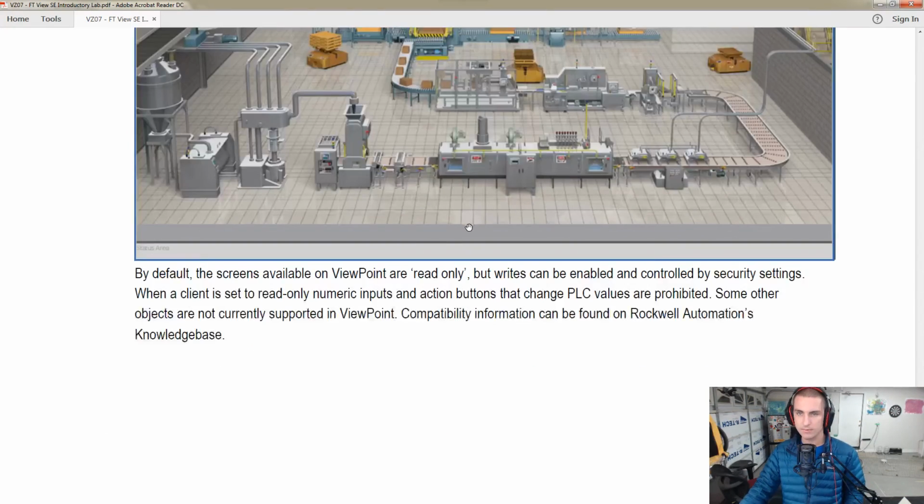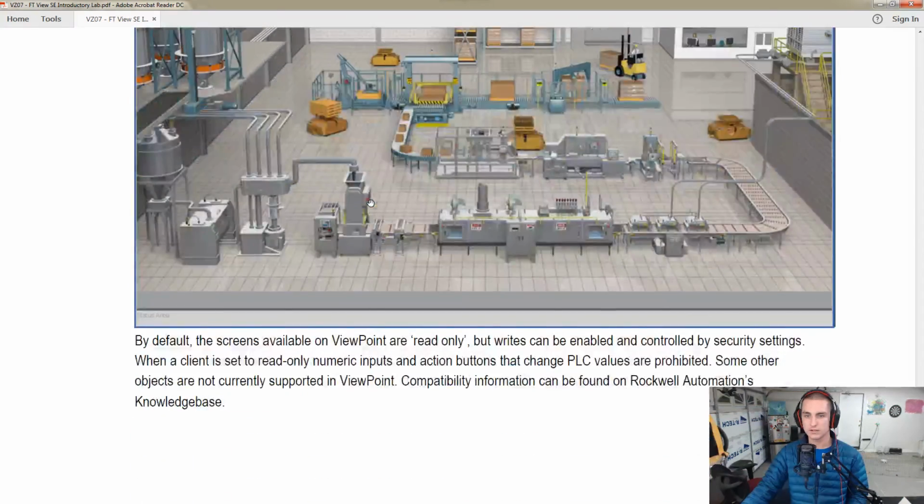But basically, assuming that's set up correctly, assuming you've gone through the installation process, or you used Rockwell's virtual appliance images that you can just load into your virtual server. Let's say you have VMware, you can drop in a FactoryTalk View server VM, historian VM. You can just drop these in, and all the software is already pre-configured. You just license it. So that could save a lot of time and prevent software installation mistakes. But yeah, I know the web server is always kind of a tricky one with any platform.